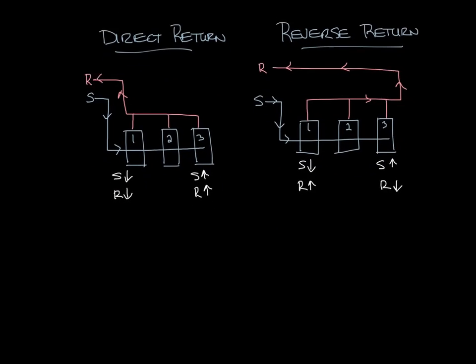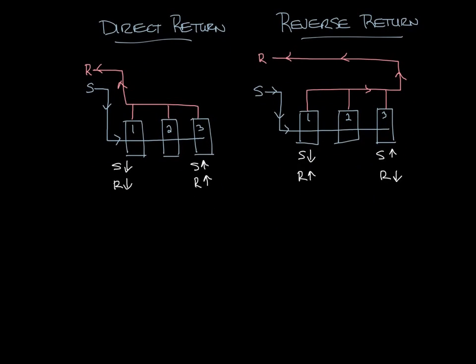Okay, so with reverse return it's an inherently balanced system. All three units have essentially the same flow regardless of flow conditions. So you have more even flow through all the units.